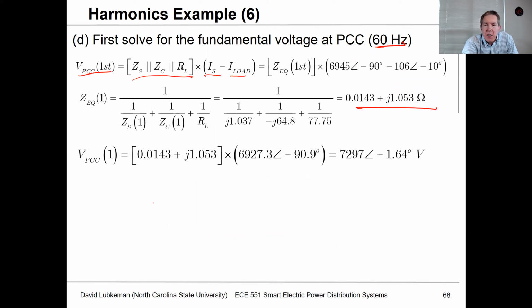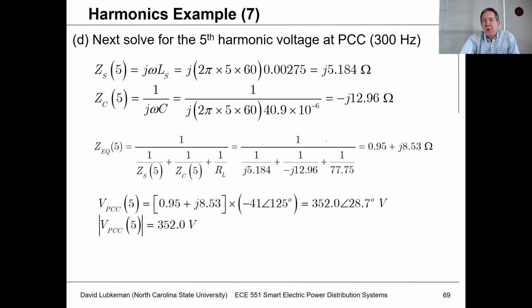at 60 hertz. If I multiply this by the equivalent injected current, I see I got 7,297 volts, right? So that's what I would have at the fundamental, which we're okay with. For the 5th harmonic, what I need to do is evaluate the source impedance and the capacitor impedance at the 5th harmonic. And so these values for the reactive impedance will be higher, the capacitive impedance will be lower. I do the same equivalent calculation for the impedance at 300 hertz.